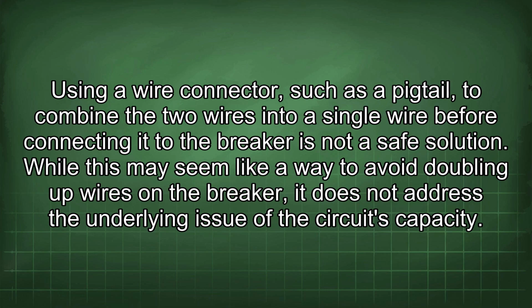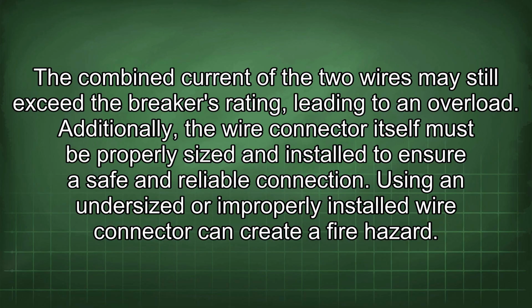Using a wire connector, such as a pigtail, to combine the two wires into a single wire before connecting it to the breaker is not a safe solution. While this may seem like a way to avoid doubling up wires on the breaker, it does not address the underlying issue of the circuit's capacity. The combined current of the two wires may still exceed the breaker's rating, leading to an overload. Additionally, the wire connector itself must be properly sized and installed to ensure a safe and reliable connection. Using an undersized or improperly installed wire connector can create a fire hazard.